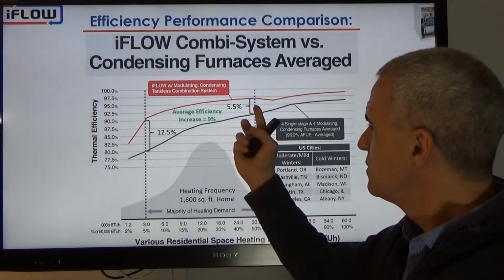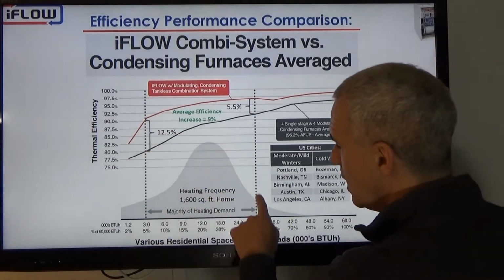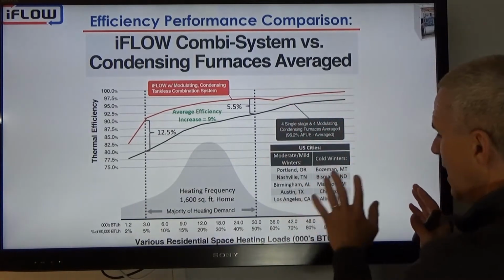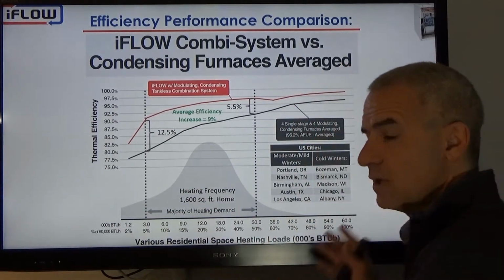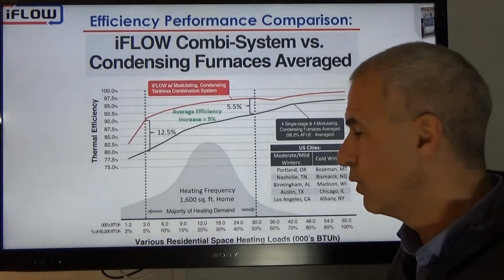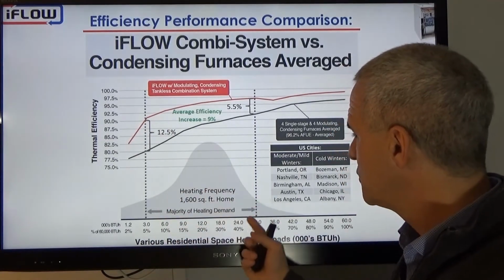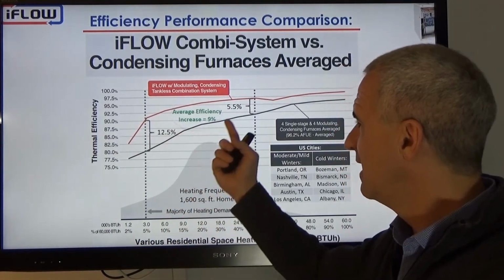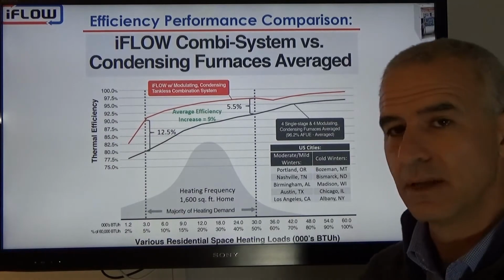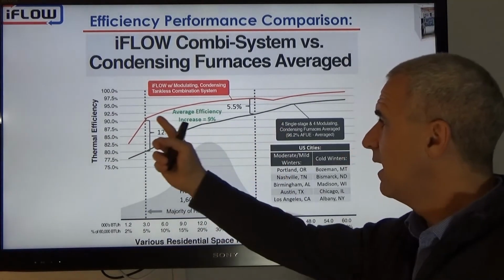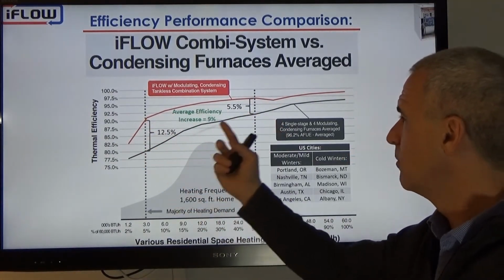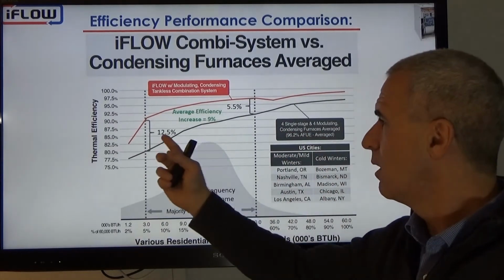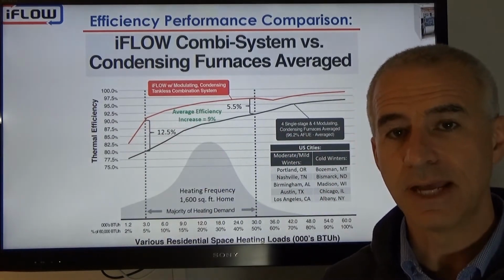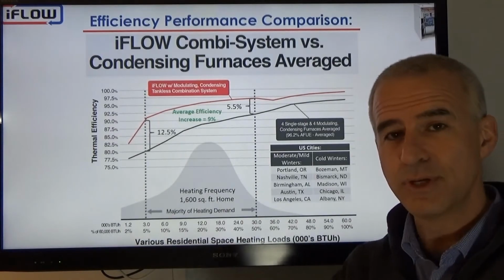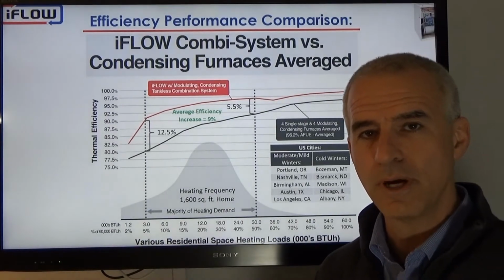So when we take these two numbers together, because this is the majority of the heating load, we're not going to worry about how it performs at maximum because we're never operating there. We're almost never operating there. We're going to look at where the actual heating load is, and there we can get an average efficiency of 9%. So what this says is the iFLOW and Navien are outperforming the best furnaces in the market by an average of 9%. And again, 7 of those 8 furnaces are presently on the Energy Star program.